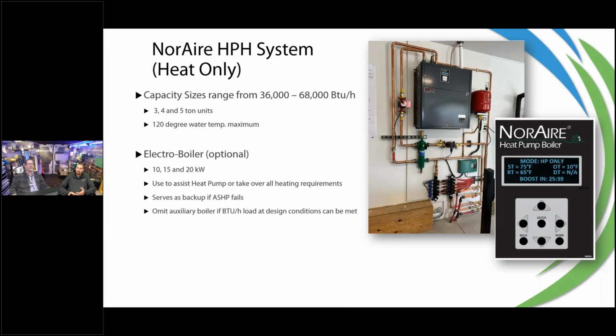So when we talk about, here's a little control picture. You can see the option there for the electric boiler and 10, 15, and 20 kW platforms there. Outdoor ranges, as far as tonnage goes, 3, 4, and 5 tons. We're talking 100. Anytime we hear air to water heat pumps, just try to keep that 120 number in your head. Could we do a little bit higher? Probably, but most of your applications is going to be 120, I'd say 100 to 120 degrees. It's going to be the sweet spot there.